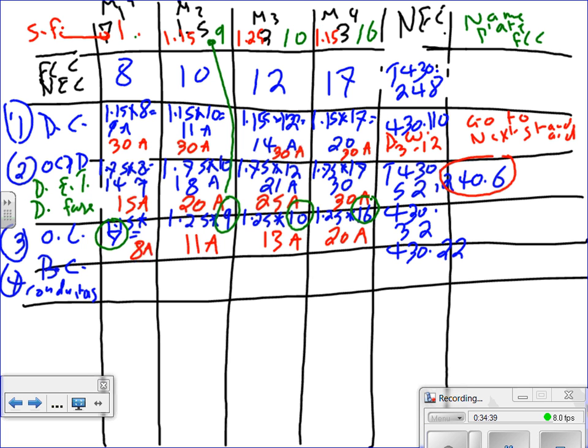430.22 and 310.16. And don't forget that you're going to go to the 75-degree column. Here are the rules for branch circuit conductors. These are motors. We go to 75 regardless of the rules. So I'm going to go to 75, and Article 430.22. If you go to Article 430.22, here's what it tells you. It's continuous load multiplied by 1.25.